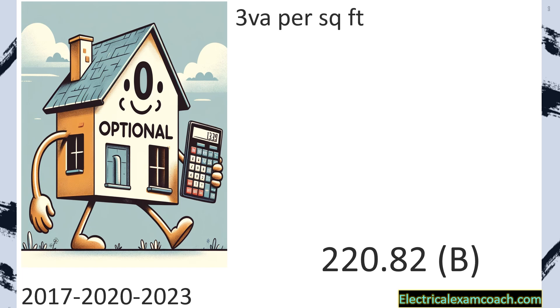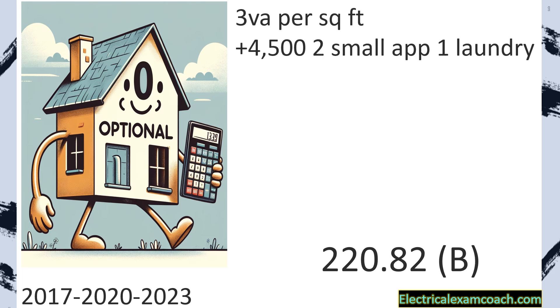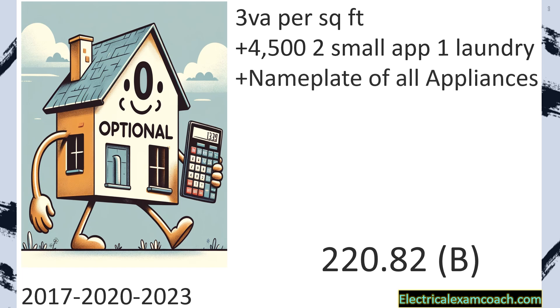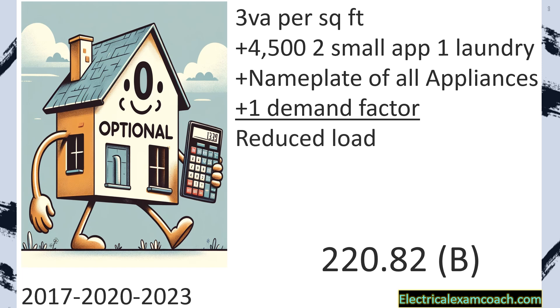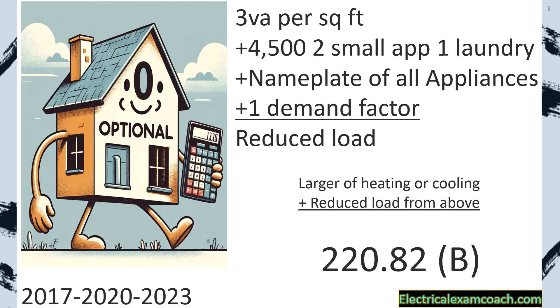We're still going to do our three VAs per square foot and our 4,500 VAs for our two small appliance and one laundry circuits. Then we're going to take the nameplate of all appliances and apply one demand factor — that gives us our new reduced load. All we have left to do is total our HVAC, take the larger of heating or cooling, add that back to the reduced load, and we have our total connected load. Let's get to it.